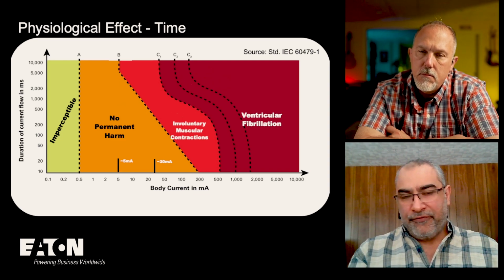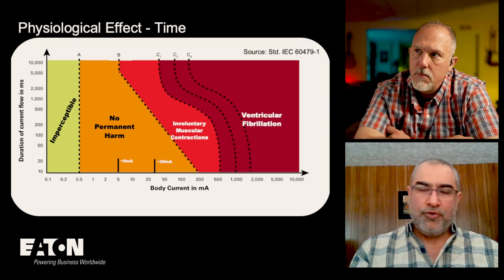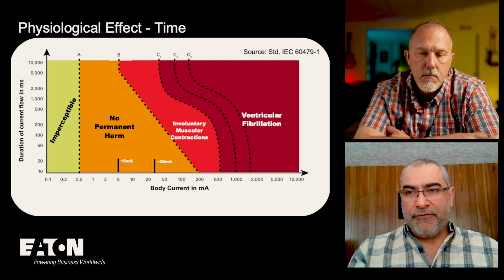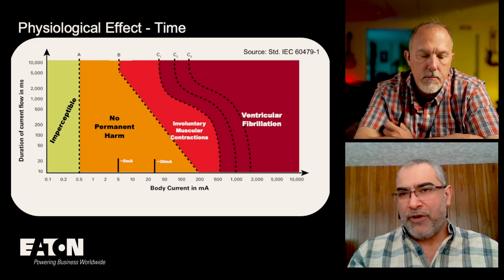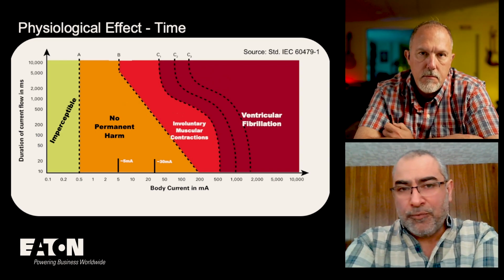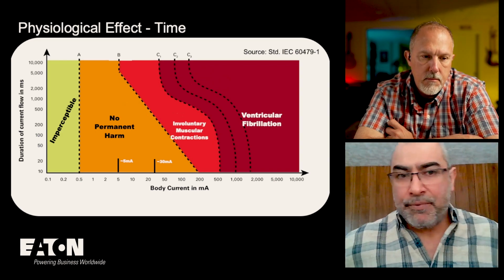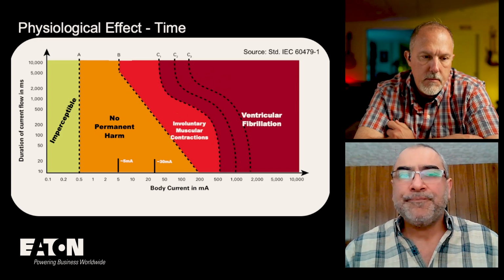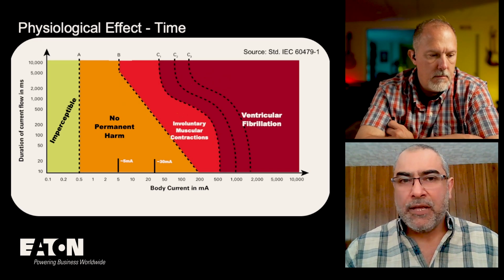If you notice, the 5 milliamp and 30 milliamp levels are more like the European versus North American trip levels. So 5 milliamp plus or minus one, some say 4 to 6 - there are different ways of saying it, but this is the GFCI trip level. We talk about 6 milliamp or 5 plus minus one, but it's the same concept.